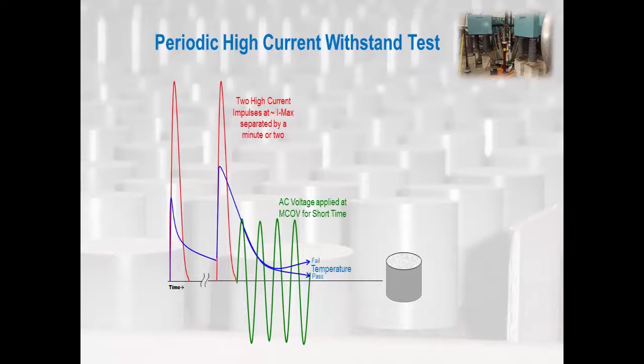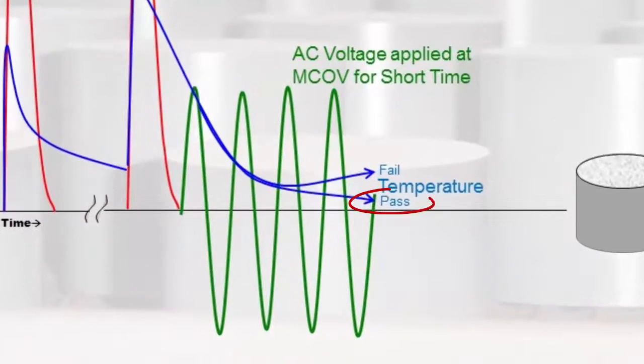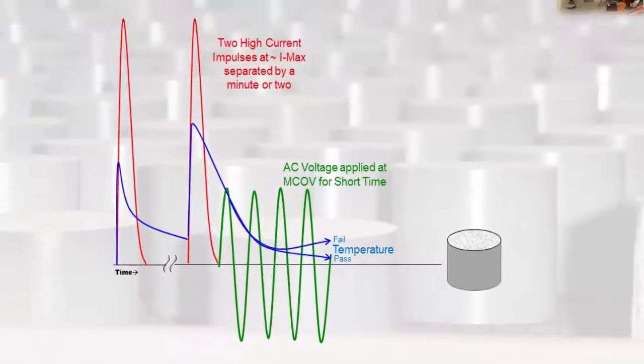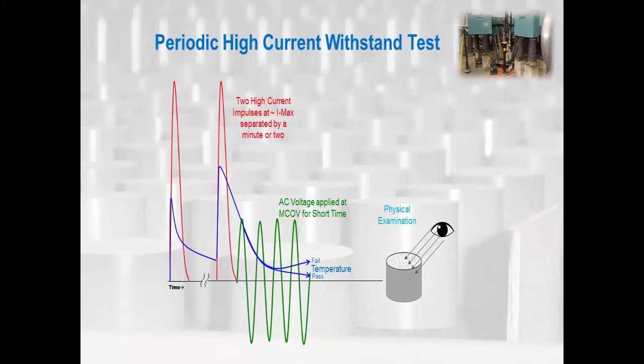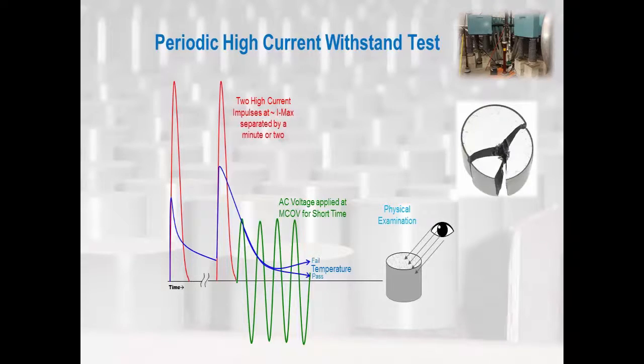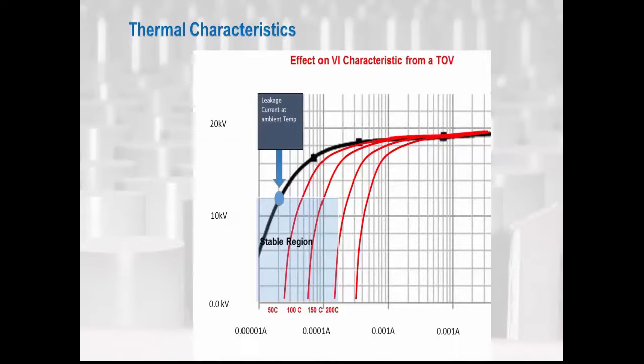If the temperature of the disc continues to drop during the brief AC application, then the disc has passed this test. The final step in this quality assurance test is a physical exam. What we don't want to see are chips or cracks in a disc. Another critical test conducted on good quality disc is one to validate the published TOV curve of the arrestor to which it will be installed. This test is not required by standards, but is certainly used by quality disc suppliers.